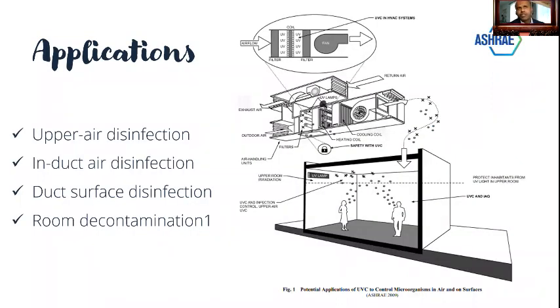Now, what is the application of UVGI within the buildings? So within the buildings and HVAC systems, UVC can be used in residential, commercial, schools, as well as healthcare facilities. Applications include upper air disinfection, in-duct air disinfection, duct surface disinfection and room disinfection all together. However, the use of UVC requires special PPE to limit accidental overexposure.